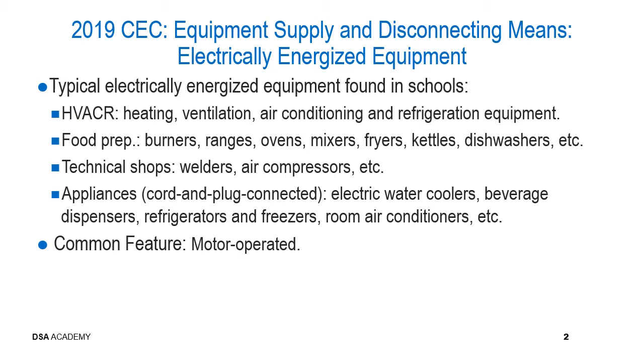Those associated with technical shops, such as welders or air compressors, etc. Those associated with appliances, specifically cord and plug connected appliances, such as electric water coolers, beverage dispensers, refrigerators and freezers, room-style air conditioners, etc. And I think we'll all agree that one of the common features for each of these pieces of electrically energized equipment is that they're motor operated. And the fact that they're motor operated introduces some additional concerns for both safety and operation of the equipment that we're going to discuss in the next few slides.